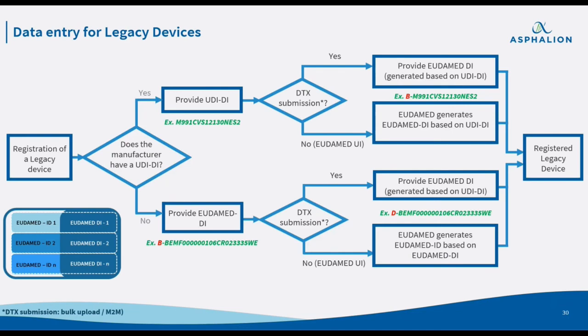Okay, so far all the process explained before applies to the so-called regulation devices. But what happens with the registration of legacy devices? Well, in these cases, it's a bit tricky because you have to remember that there is the possibility that a legacy device is already having a UDI. So this is the first step. If you want, we can divide this diagram in two parts.